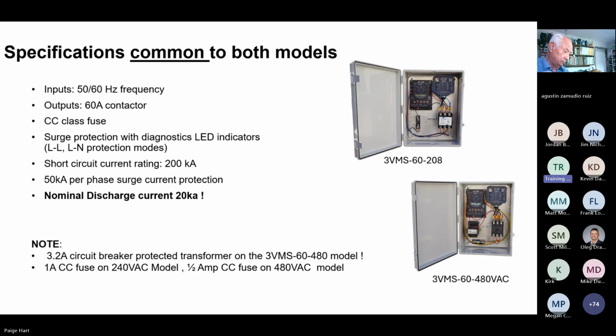And again, I bolded that one because that's a big deal. That is really the key factor saying that this is a very durable device that can take many hits over time. And that's the UL rating for that durability rating. So as I mentioned, there's a 3.2 amp circuit breaker in the step down transformer. And we see those 1 amp and 1/2 amp fuse ratings for the different models.